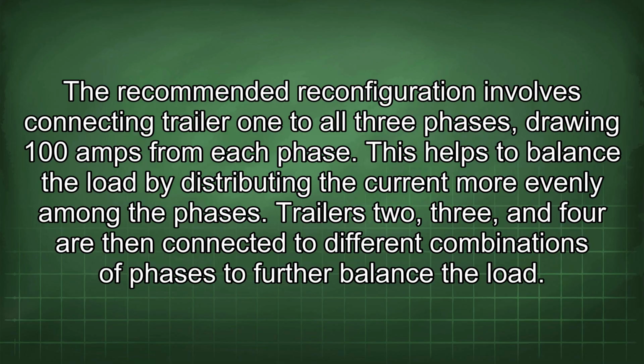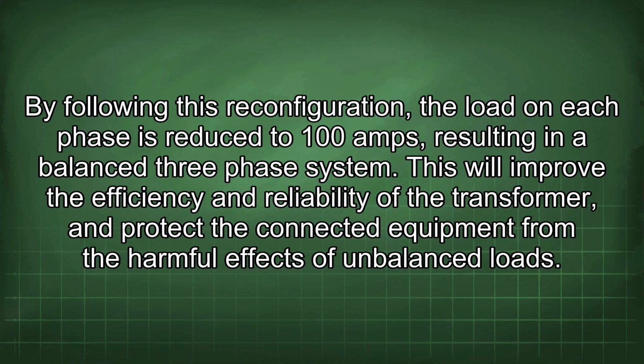The recommended reconfiguration involves connecting trailer 1 to all 3 phases, drawing 100 amps from each phase. This helps to balance the load by distributing the current more evenly among the phases. Trailers 2, 3, and 4 are then connected to different combinations of phases to further balance the load. By following this reconfiguration, the load on each phase is reduced to 100 amps, resulting in a balanced 3-phase system.